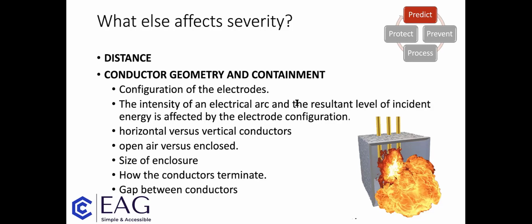So the other issues that affect the arcing current and the incident energy is horizontal conductors versus vertical ones, open air versus enclosed, the size of the enclosure, how the conductors terminate, and also the gap between the conductors themselves.